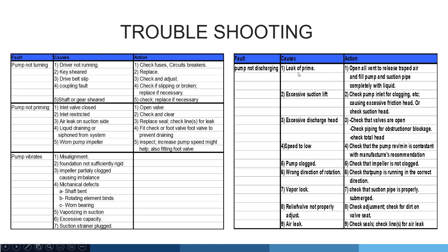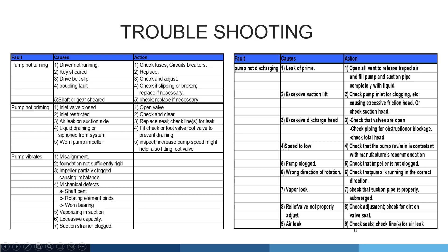Pump not discharging. First check for loss of prime — open all vents to release trapped air and fill the pump suction pipe completely with liquid. Check for excessive suction lift — inspect the pump inlet for clogging causing excessive friction head, or check the suction head. Check for excessive discharge head — ensure valves are open and check piping for obstructions or blockages. Check that the pump RPM is consistent with the manufacturer's recommendation. Check that the impeller is not clogged. Check that the pump is running in the correct direction. Check that the suction pipe is properly submerged to avoid vapor lock. Check and adjust the relief valve and inspect for dirt on the valve seat. Check seals and lines for air leaks.